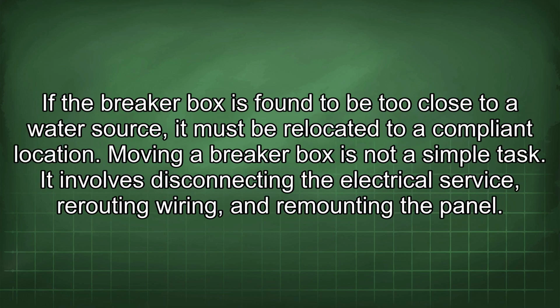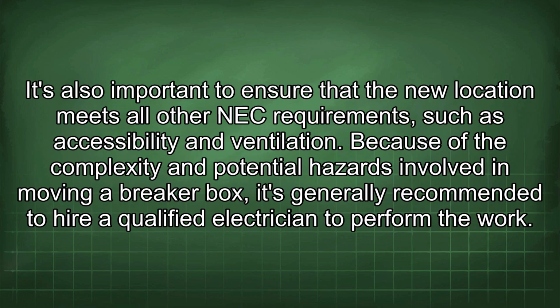If the breaker box is found to be too close to a water source, it must be relocated to a compliant location. Moving a breaker box is not a simple task. It involves disconnecting the electrical service, rerouting wiring, and remounting the panel. It's also important to ensure that the new location meets all other NEC requirements, such as accessibility and ventilation. Because of the complexity and potential hazards involved in moving a breaker box, it's generally recommended to hire a qualified electrician to perform the work.